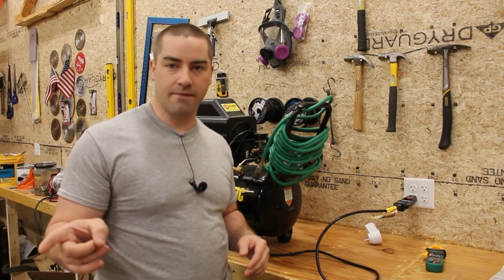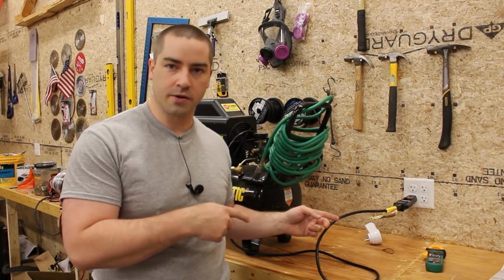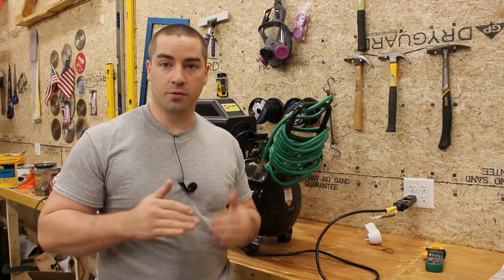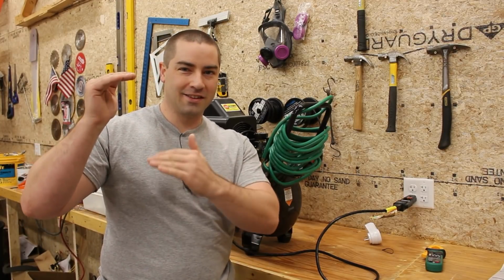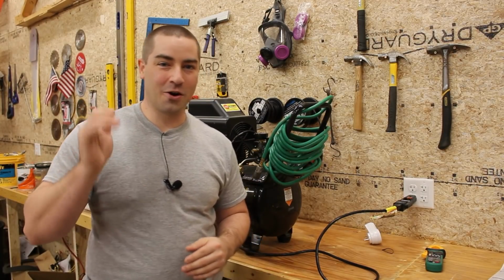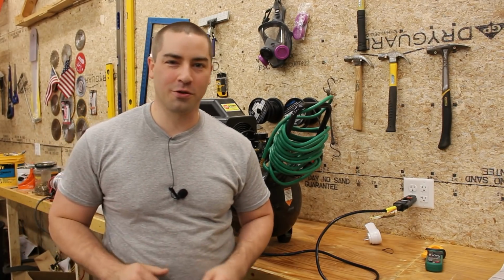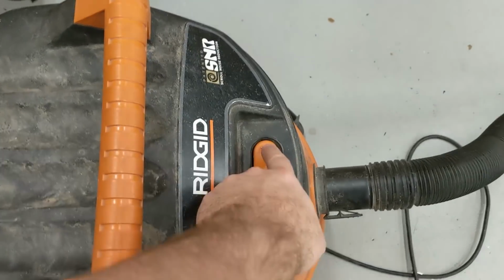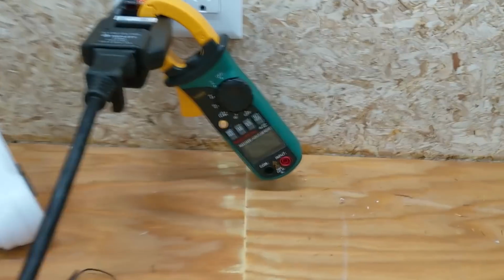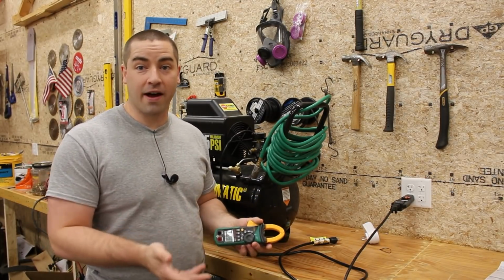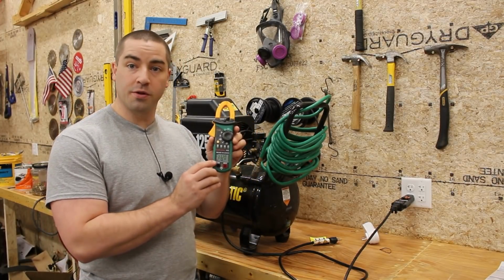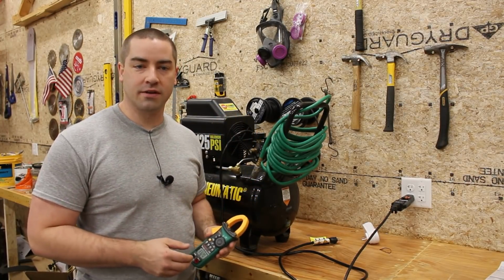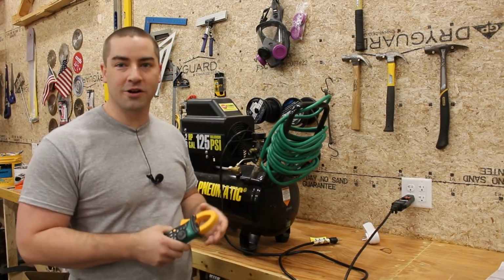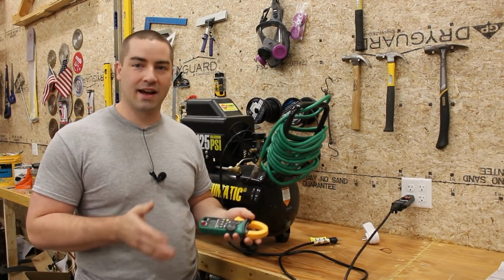Let me pull the shop vac cord over here and run the shop vac also, that way we know what it can do. We'll try to narrow the can't to the can, the go, no-go, and find out where the threshold is. We'll find out the shop vac... there we go. 33.2 - so the wet dry vacuum, or shop vac as a lot of people call them, drew 33.2 amps during its inrush. So we're getting a fairly small margin now of what the Bluetti can and cannot power.